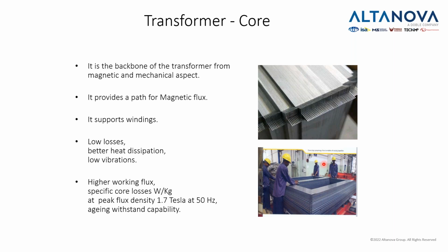It holds the transformer, and the windings are wound around these parts of the core. So it supports the windings. It needs to have low losses, better heat dissipation, and low vibrations. The sound you hear when you approach the transformer is the sound you get if these are not very well tightened, if they're not pressed together.